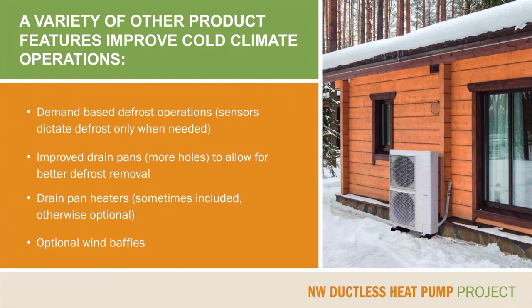In addition to specially designed computer controls and variable capacity components, cold climate ductless heat pumps have other features that make them ideal for cold climate operations. These include enclosures that drain condensate better than earlier generations, and controls for their defrost cycle that limit defrost cycle operation only to the times that is necessary, and for only as long as necessary. Drain pan heaters, as well as optional wind baffles, can be important components that help make cold climate variable capacity heat pumps operate at peak performance.